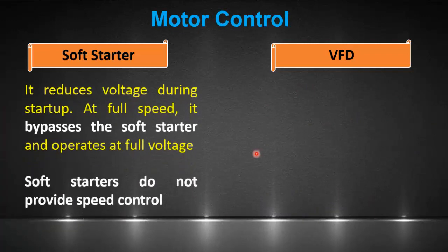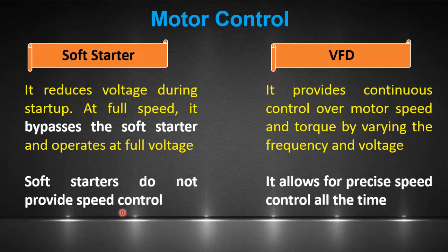A soft starter only controls the voltage supply to the motor during startup and initial acceleration. Once the motor reaches the desired speed, it bypasses the soft starter and operates at full voltage. Soft starters do not provide speed control. A VFD provides continuous control over motor speed and torque by adjusting the frequency and voltage supplied to the motor at all times, allowing for precise speed control in continuous operation.